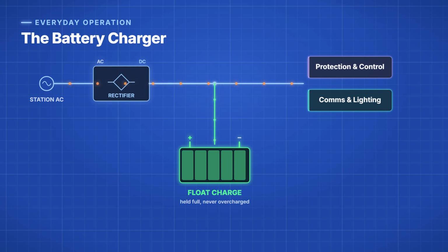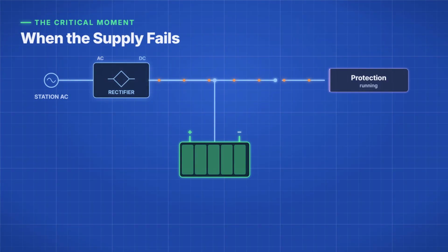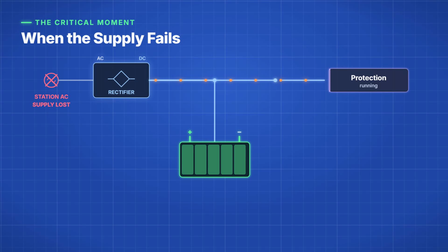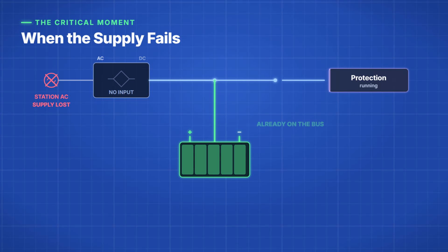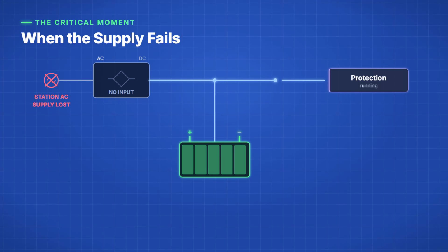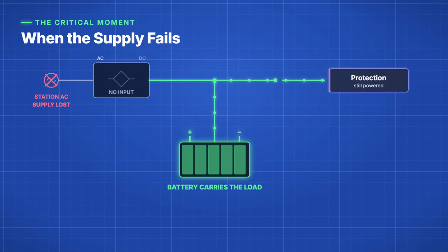So in normal operation, the battery barely does anything. It simply floats across the bus, fully charged, waiting. If the battery has been drained, the charger can raise its voltage for a while to recharge it faster, and that's called a boost charge. Now, we can answer the question we started with. What happens when the incoming supply fails? The charger has no input, so its output falls away, but the battery is already connected across the bus, floating there the whole time. So the moment the charger drops out, the battery simply carries the load.